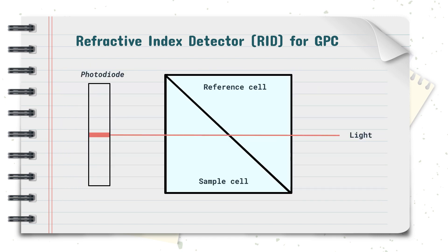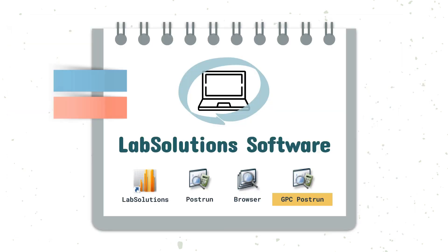As solutes elute out from the column and into the sample cell of the detector, the composition of the mobile phase in the sample cell changes, causing the light beam to refract due to the difference in refractive index. This results in a horizontal shift in the image produced on the photodiode, the distance of which is proportional to the difference in refractive index between the sample and reference cell.